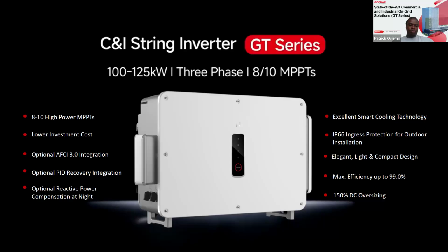That's the AFCI 3.0. It's AI driven. So we can sense arcs very far away from the inverter, up to 200 meters from the inverter. Very low surges, we can still sense this before it gets into the dangerous levels. So AFCI. PID, potential induced degradation for your panels, is also optional for those who are working in hot and humid conditions. Reactive power at night. If you have issues in terms of power factor values, then you can offset this during the night and restore your power factor to the required standards.